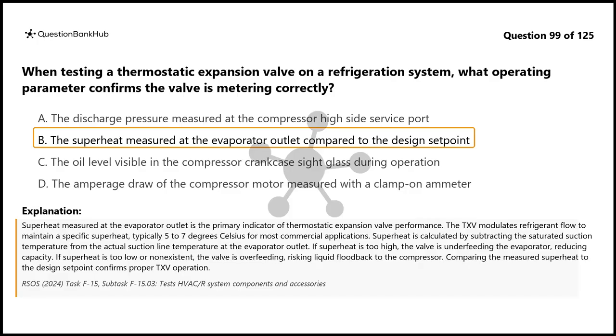If superheat is too high, the valve is underfeeding the evaporator, reducing capacity. If superheat is too low or non-existent, the valve is overfeeding, risking liquid flood back to the compressor. Comparing the measured superheat to the design setpoint confirms proper TXV operation.